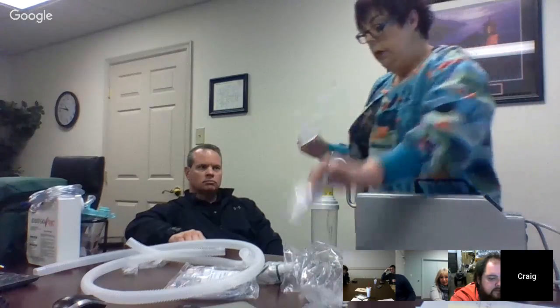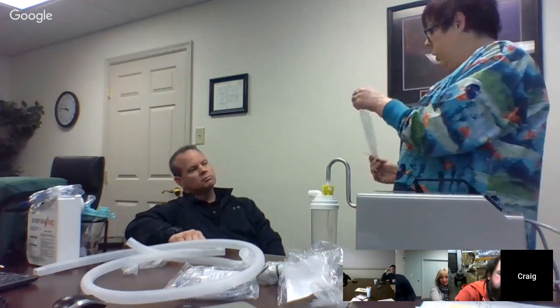There are a few other pieces that you'll put together for this. This is your water trap. What this is going to do is if there's any moisture or water, this is going to catch it, okay? So it's very important that when you get water in this, you open this and drain it out. Drain it into a bowl, a garbage can, whatever, and then push this back in so it's nice and tight and closed, okay? You don't want this to get filled up. If this fills up, you're going to have excess water in the tubing also, and it's just going to cause this blooping noise, bloop, bloop, bloop, and you're going to think that something's wrong with the machine.